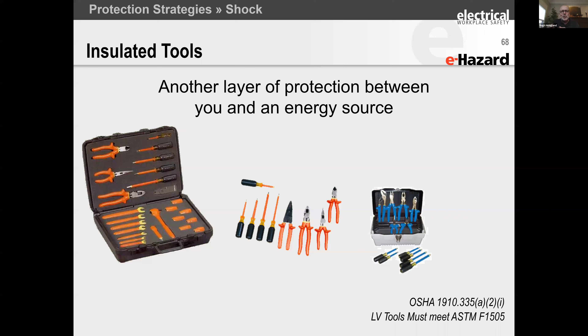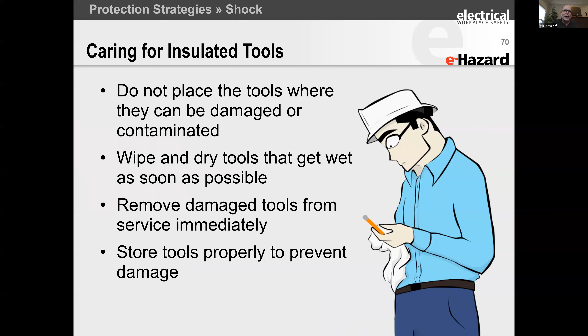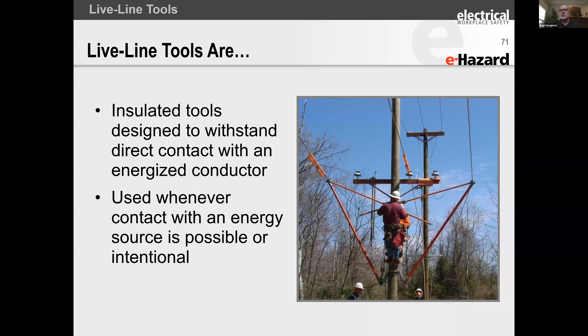But most companies don't. They just stick them in a tool pouch, but then you're scarring those tools every time you use them. It's really good to take very good care of these tools. One, they're expensive, and two, they can be damaged quite easily. And then, of course, all these are hot sticking tools that are used in the US and around the world. These types of tools have to be tested regularly. In the US, it's required by law that they be physically tested every 24 months and that they be inspected by a second person who is qualified to determine if there's any scarring that would cause this tool to fail. And then, of course, they're inspected every single time you use the tool.